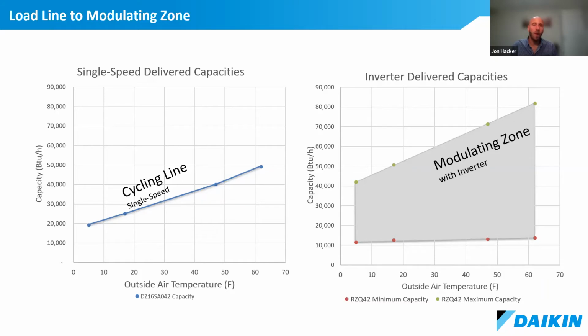What we're showing here is that a single speed heat pump can only provide one capacity at any given outdoor condition. Looking at this graphic, if I look at the 47-degree outdoor temperature condition, that heat pump can provide 40,000 BTUs of heat, and that's it. It will provide comfort by turning on and off to maintain comfort, but it can only provide 40,000 BTUs at that condition. The other thing that you'll notice, which will be important later on as we drive down to applications, is that the heat pump's ability to deliver heat does diminish as the temperature decreases, right?